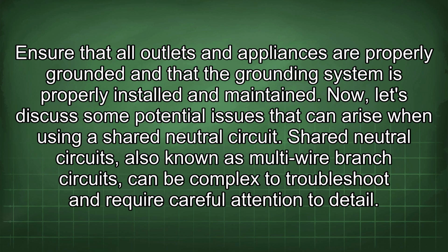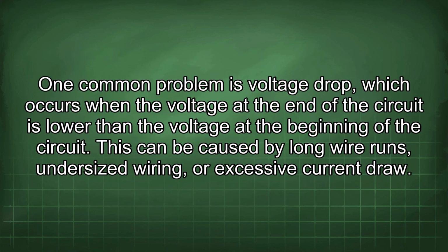Now, let's discuss some potential issues that can arise when using a shared neutral circuit. Shared neutral circuits, also known as multi-wire branch circuits, can be complex to troubleshoot and require careful attention to detail. One common problem is voltage drop, which occurs when the voltage at the end of the circuit is lower than the voltage at the beginning of the circuit. This can be caused by long wire runs, undersized wiring, or excessive current draw.